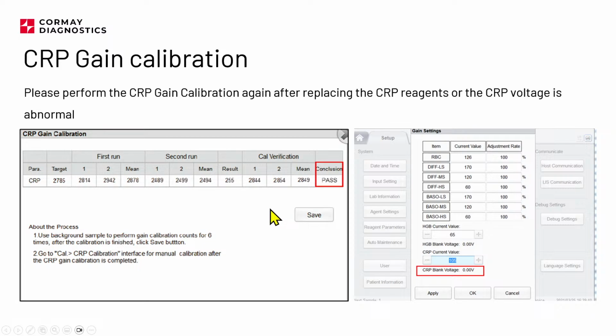It will take, I don't know, 5 or 10 minutes, and then the analyzer will tell you if the test was passed or failed. If the test failed, it means that maybe the chamber is dirty, or maybe the CRP line is still not primed correctly with the CRP reagent. So you just need to check those 2 possibilities. But when the test is passed, you just need to save it, and right now the device will have a new reference level for the background.